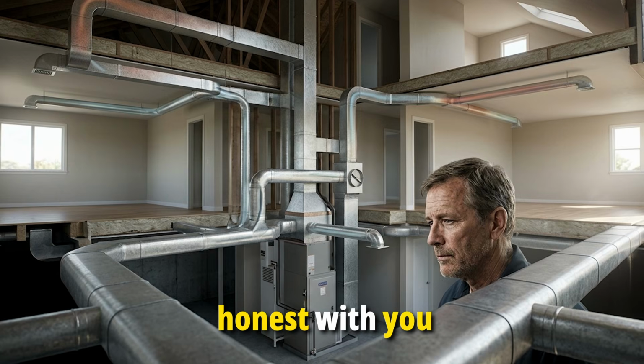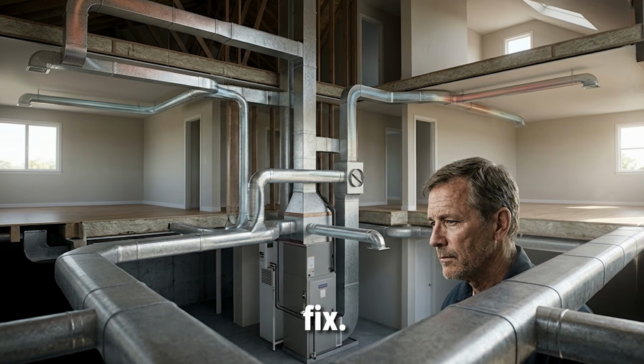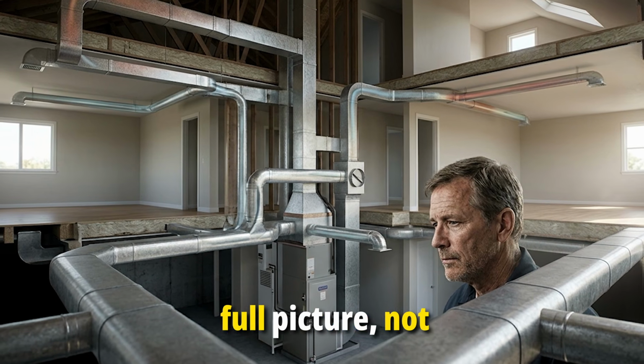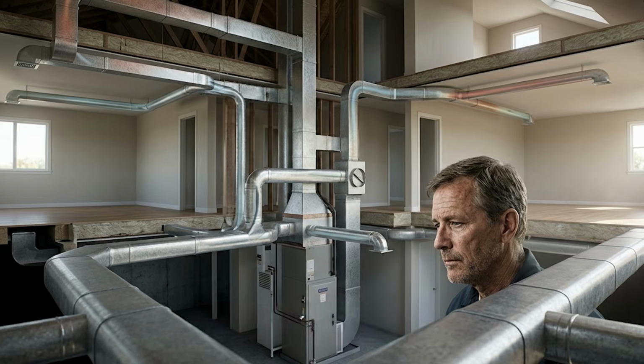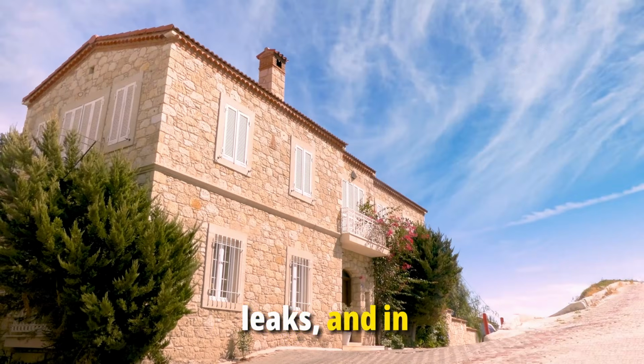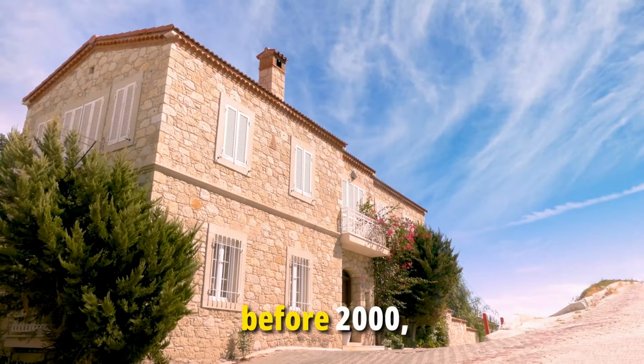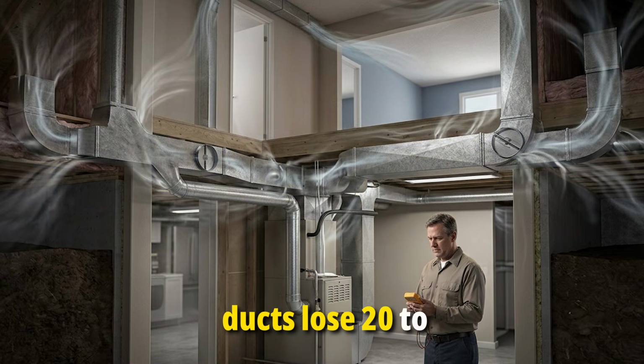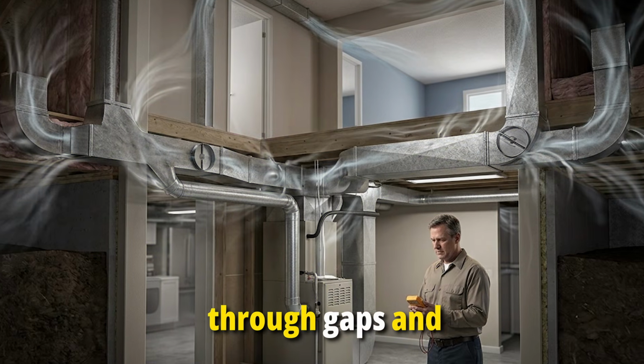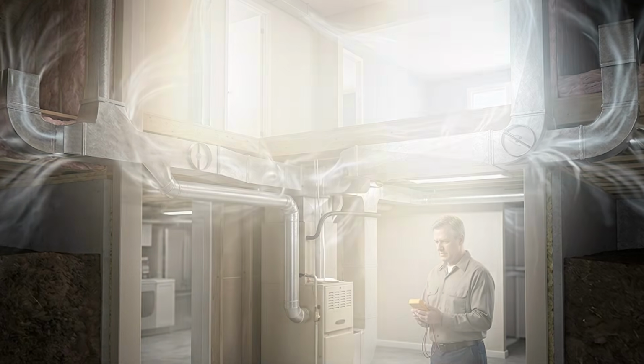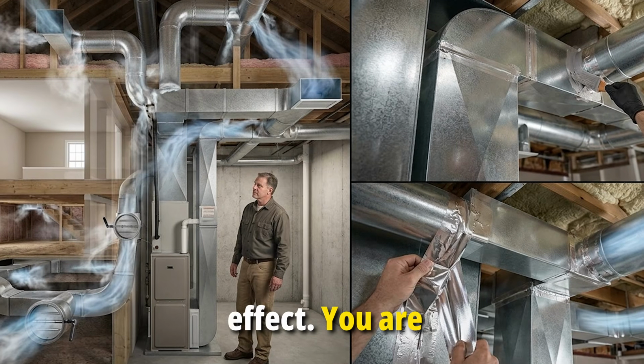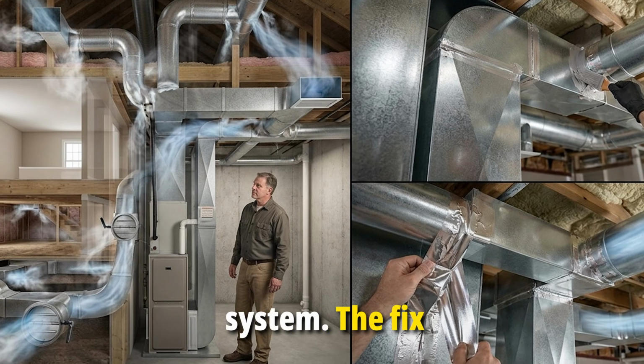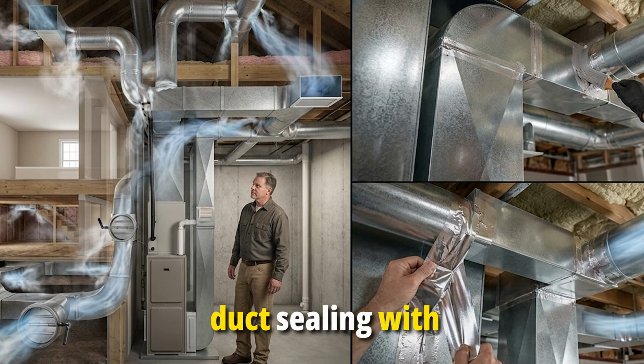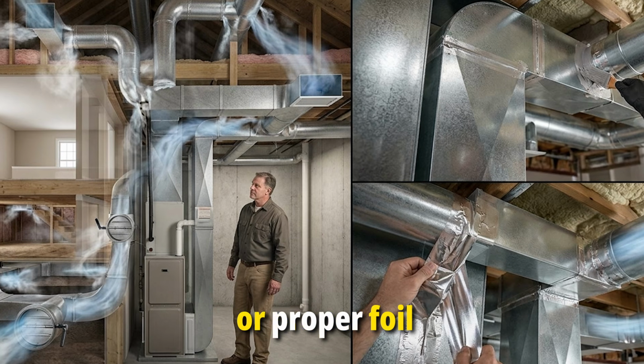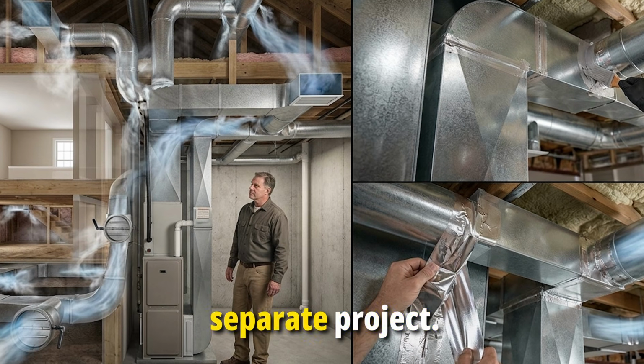Now I want to be honest with you about what damper balancing cannot fix, because I think you deserve the full picture, not just the parts that sound good. If your ductwork leaks, and in most homes built before 2000, ducts lose 20 to 30% of conditioned air through gaps and poorly sealed seams, adjusting dampers has limited effect. You are balancing a leaky system. The fix for that is duct sealing with mastic compound or proper foil tape, which is a separate project.